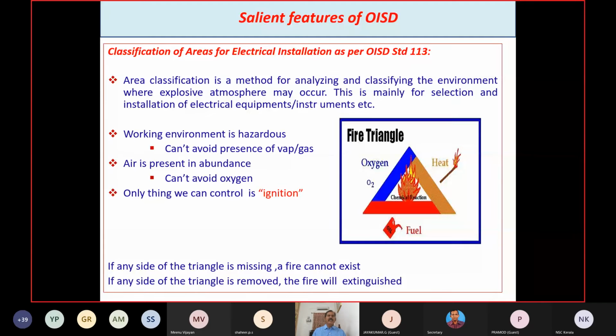So if you go to any oil or gas industry, you can see the hazardous area and non-hazardous area. It will be bifurcated. The plant area will be hazardous and the rest non-hazardous. Nobody can enter the hazardous area. Only authorized persons are allowed inside. Even if you want to go inside, you will be checked by security, and all sources of ignition, cameras, mobiles, and all igniting material and battery operated items are prohibited.